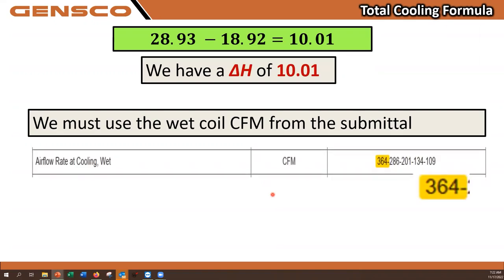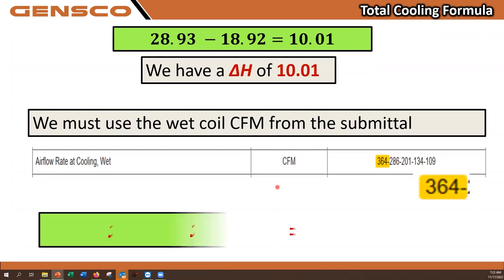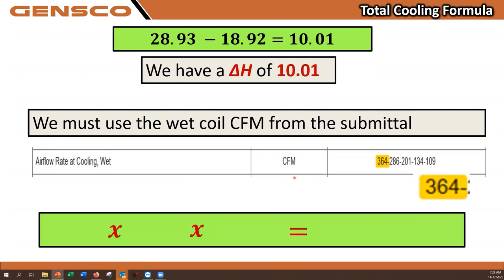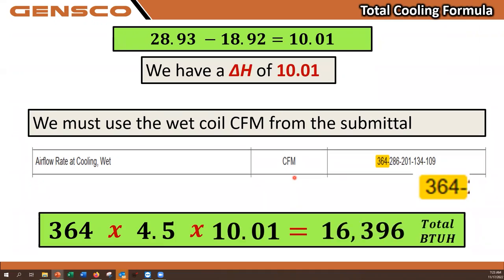The rating for a wet coil, 364 CFM. We're going to throw this in our formula, 364 times the constant, 4.5 at sea level, times our change in enthalpy, 10.01, and the result is we are producing 16,396 BTUs total cooling.